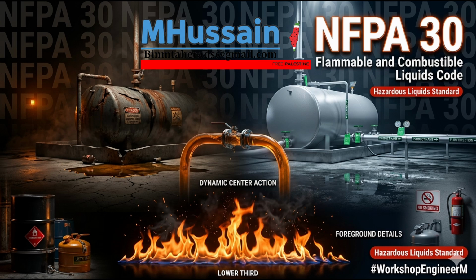Which leads to this brilliant, counterintuitive piece of engineering deduction. As a fire protection engineer, reviewing the devastation of a non-relieving steel drum BLEVE, I have to make a calculated choice. I realize I actually want my container to fail early. Yes. I want the plastic IBC to melt into a puddle at 300 degrees. I want the fusible plugs on my metal drums to pop out and actively spill their highly flammable contents directly into the fire. It's a profound realization, isn't it? You are intentionally opting to feed the fire. But the logic is impeccable.